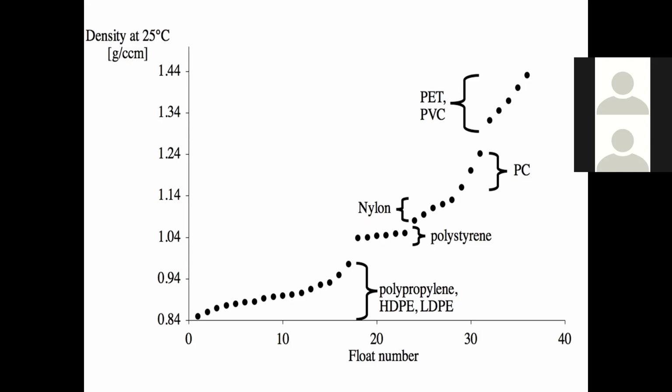In this way, when you join all these float points, you will get a straight line. If these floats are not coming in a straight line, it means your column is not working properly. If the column is correct, when you join the positions of all floats, they will come in a straight line.